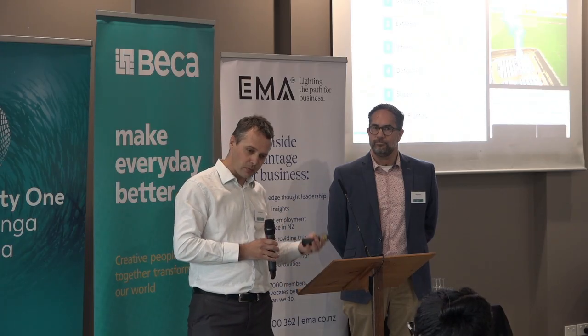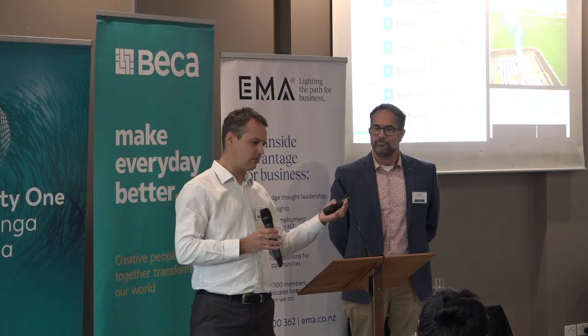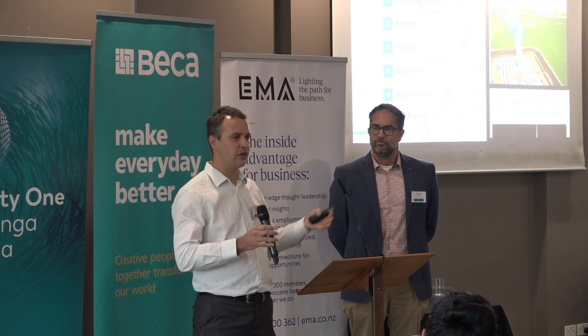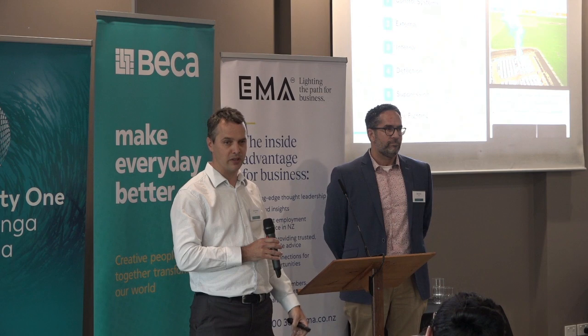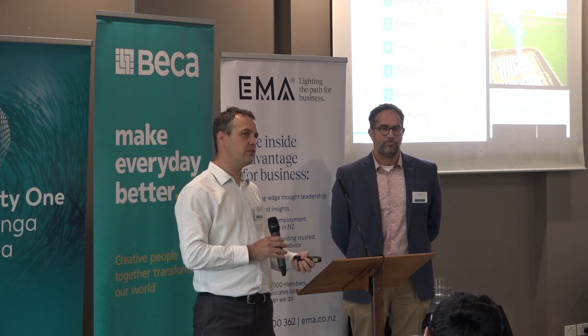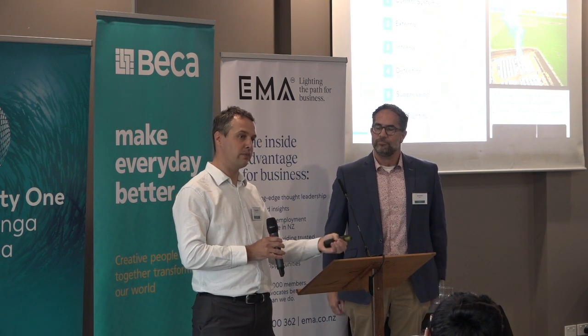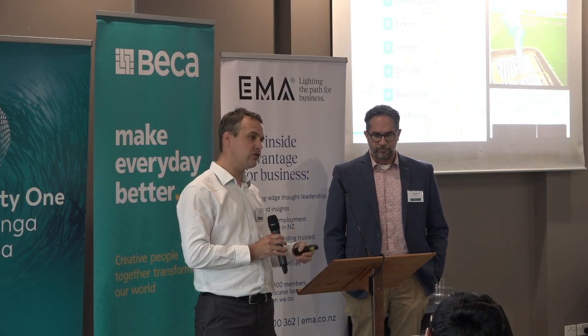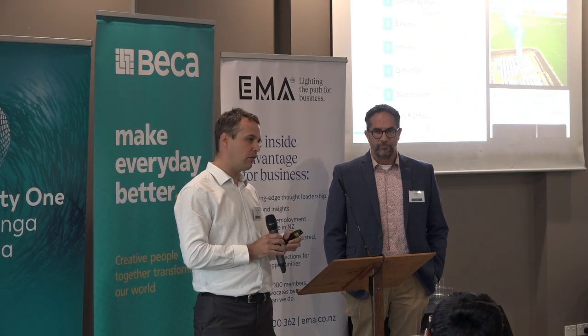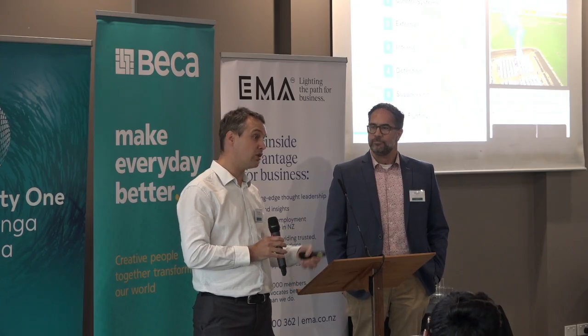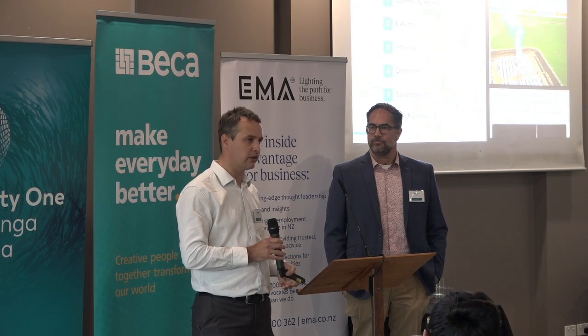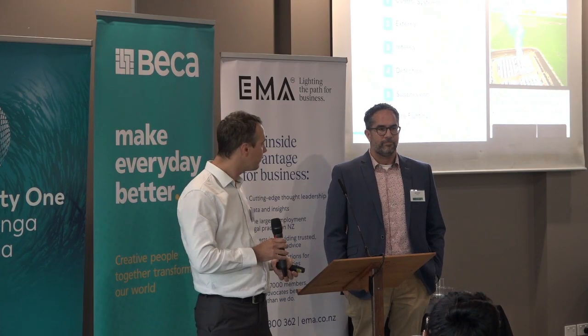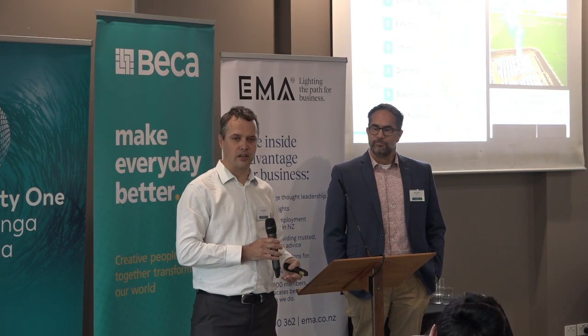Fire suppression systems - we often hear people say, it's fine, I've got an inbuilt fire suppression system in my BESS. Those systems are there to deal with the electrical fire, not the battery fire. Many of these fires start within the electronics, within the switchboards, and those suppression systems will deal with those. That will hopefully stop it getting to the battery, but once the battery is involved, you're still in for a long few days.